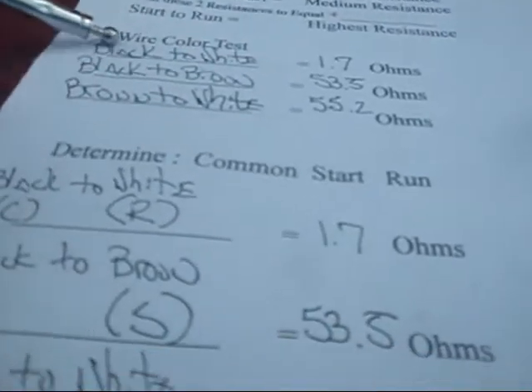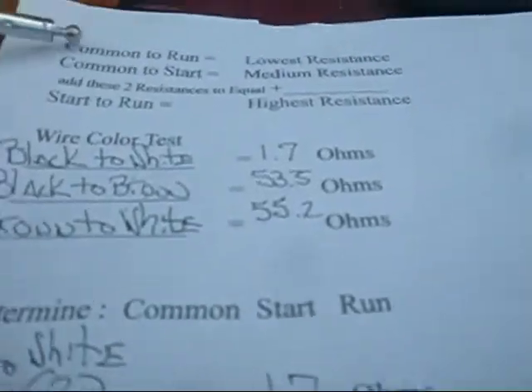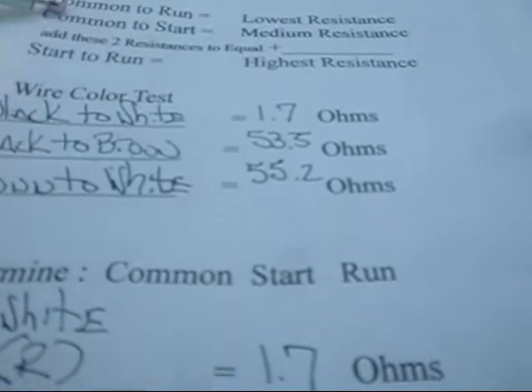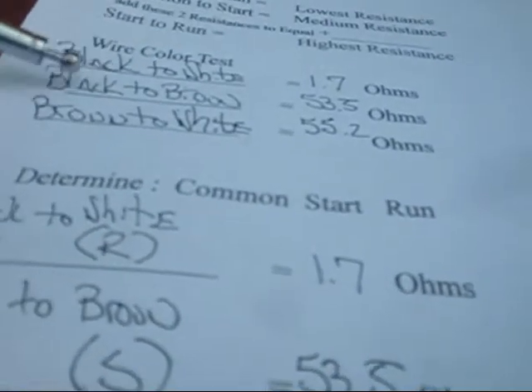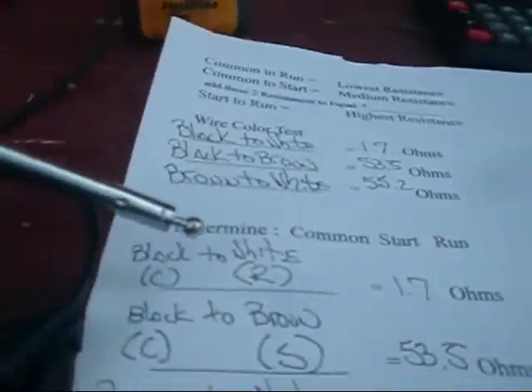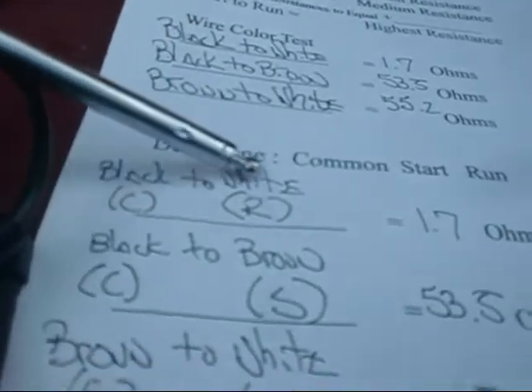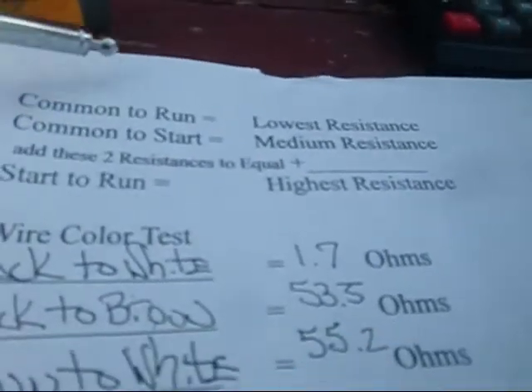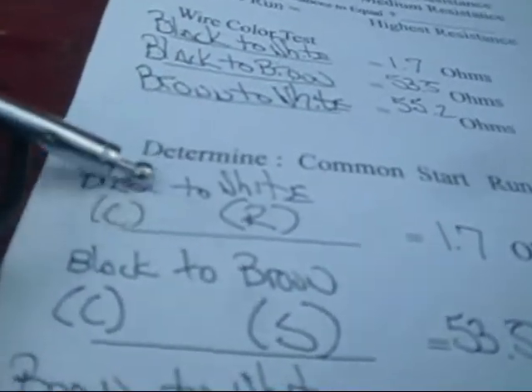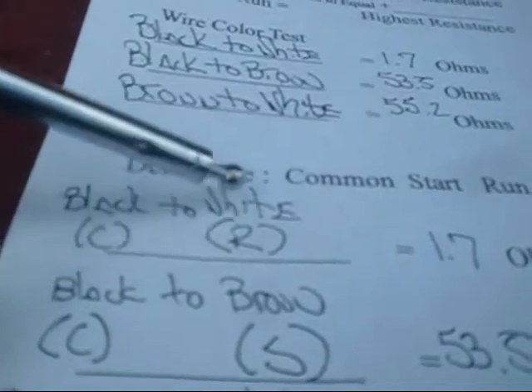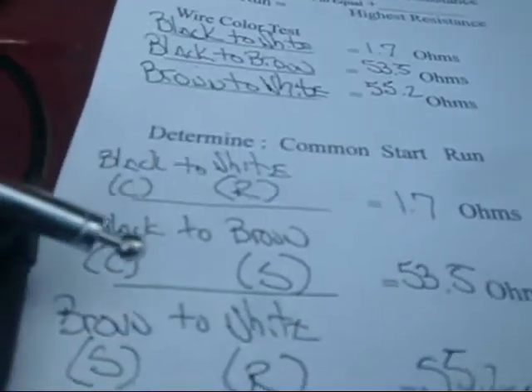So what we did out of this was we were actually trying to determine what was what. If you notice, we see this black twice here, and if you look up here, we see our common twice. This indicates what our common is. So now we've determined black to white, common to run. So now we know black is common, white is run, and that was 1.7.